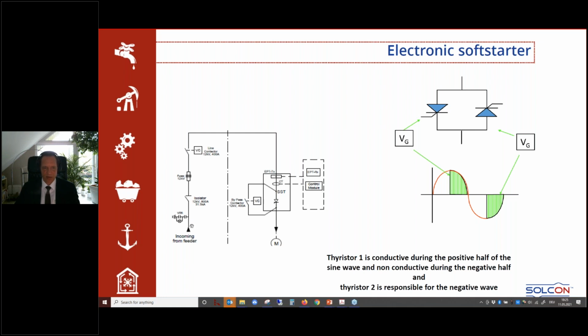You have incoming from the feeder, you have an isolator switch if needed, you have fuses, and you have a vacuum contactor, which we call line contactor. Then we have the electronic soft starter with the control electronics, and you have here the bypass contactor. So how is soft starting going on? This one is closed. This one is closed, and the bypass is open. You are starting then the electric motor via the soft starter until the bypass later on is closed.